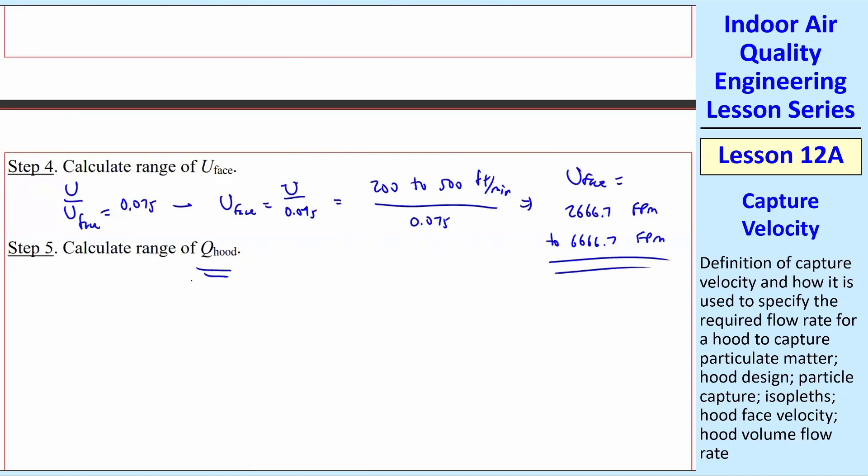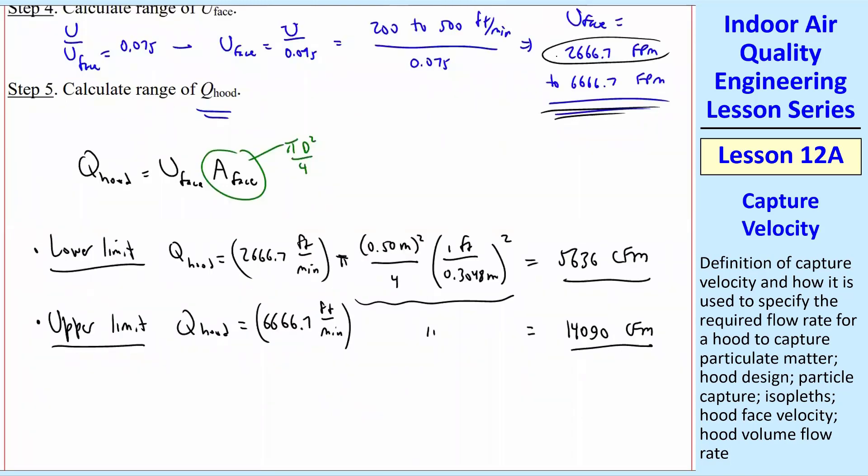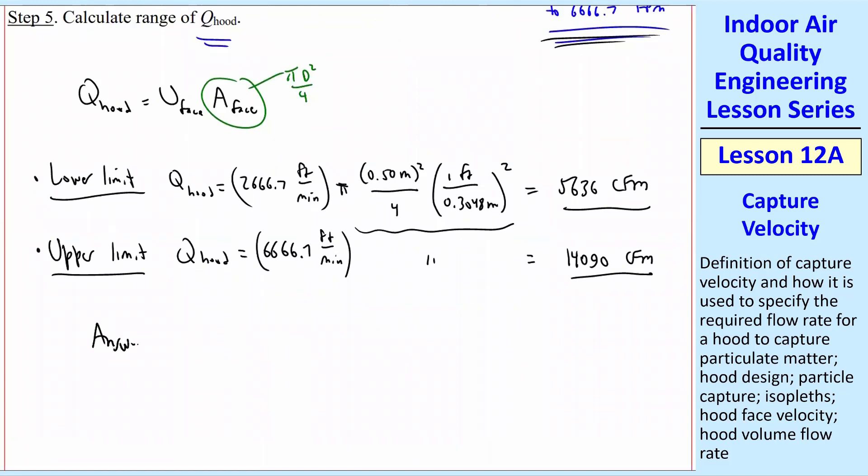And then finally, calculate the range of Qhood. So you know how to do this already from previous examples. It's just Qhood is equal to Uface times Aface. Aface is pi D squared over 4. So let's do the lower and upper limits. I'll use the lower value, and that gives me 5,636 CFM. And then you repeat for the upper limit. That gives us about 14,090 CFM. So my final answer, since I asked for a range, is 5,600. I'm rounding to two digits here, to 14,000.